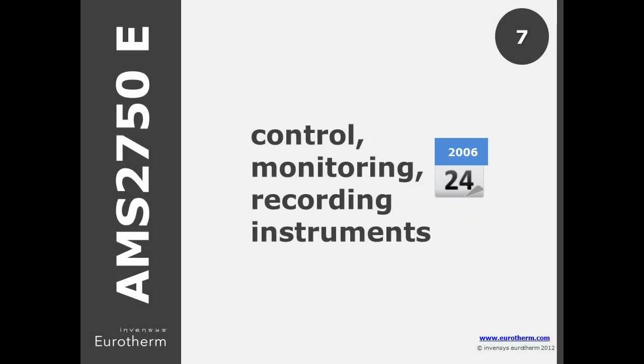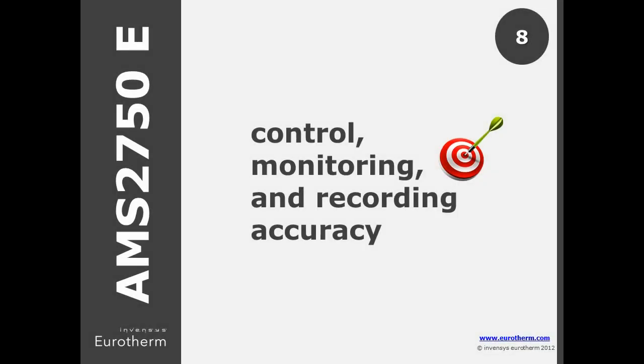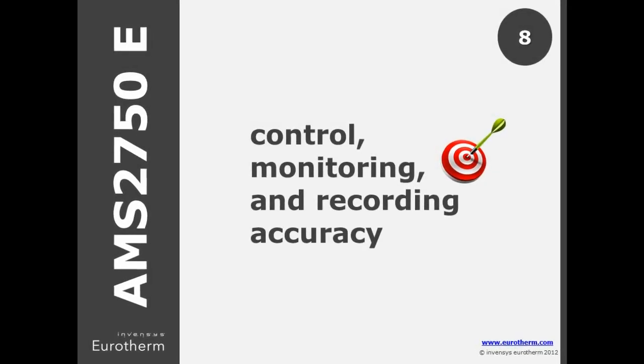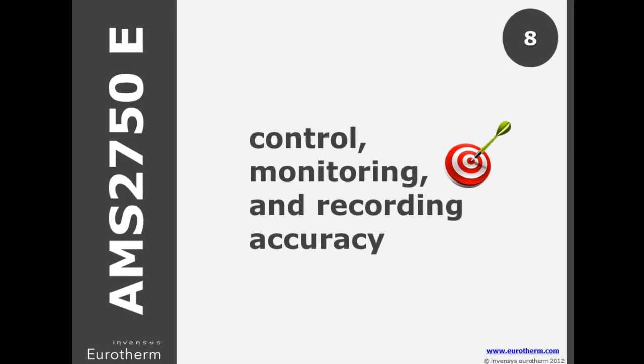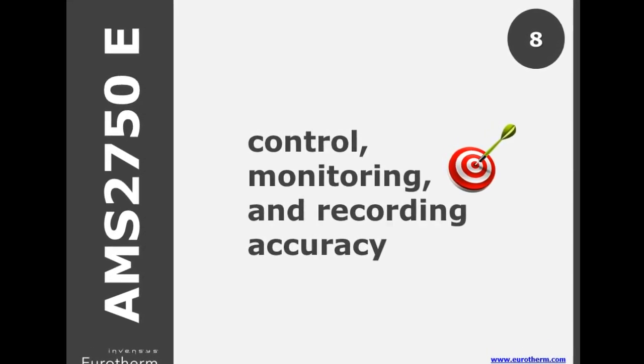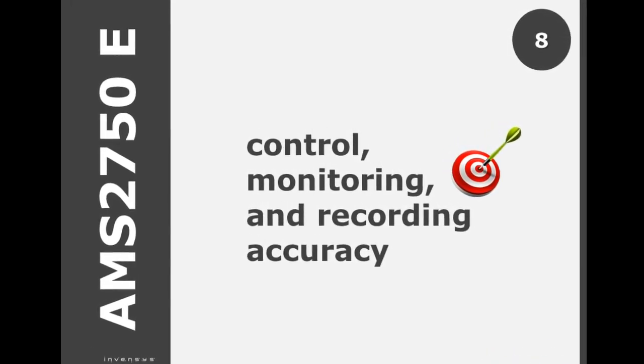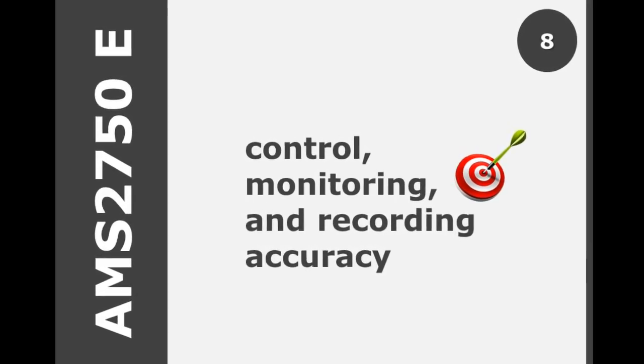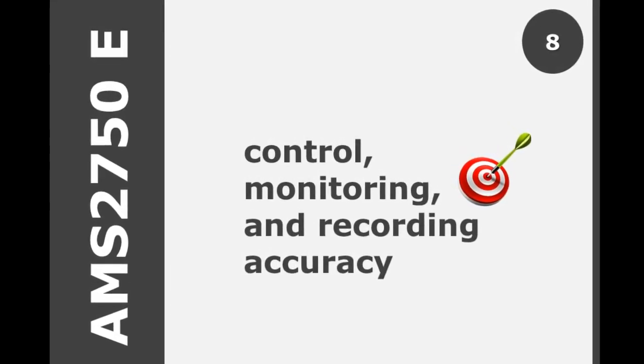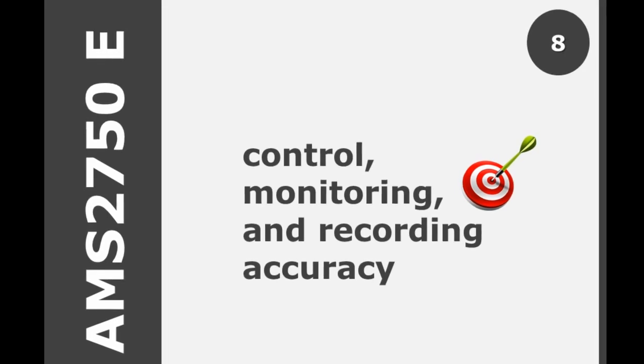If you purchase these types of instruments before September 2006, you may continue to meet the requirements of AMS2750C, but now E states a deadline of July 2015 to conform to the latest specs. Digital instruments for controlling, monitoring or recording instruments had to meet an accuracy of plus or minus 2 degrees Fahrenheit throughout the operating range. Now E specifies plus or minus 2 degrees Fahrenheit or 0.2%, whichever is greater.